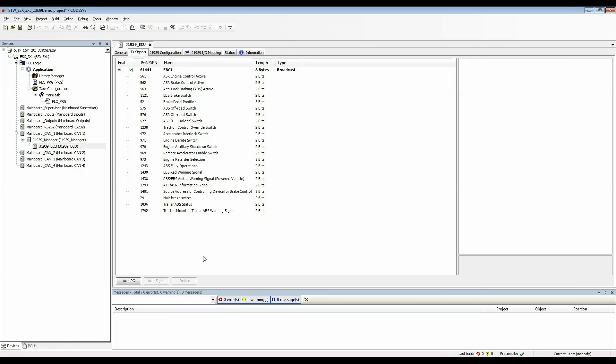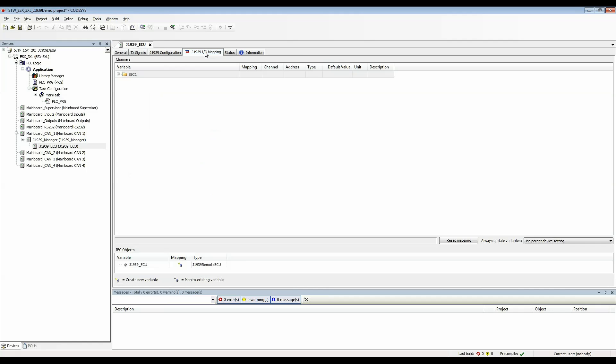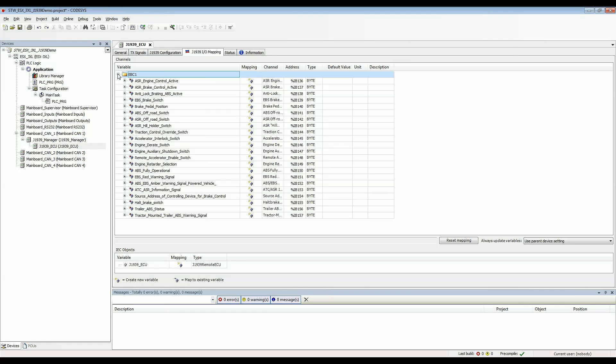If we go to the J1939 IO mapping tab we can see the PGN that we've selected and then when we open it we see all of the global variables that are created for the SPNs. The arrow pointing into the box here indicates that these are all inputs meaning that we can read these variables as incoming data to the controller.